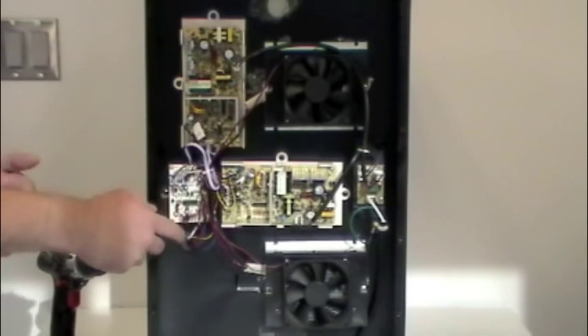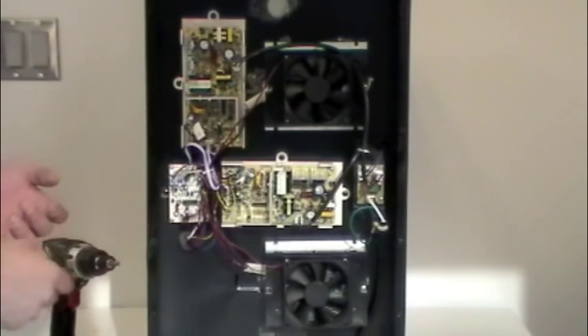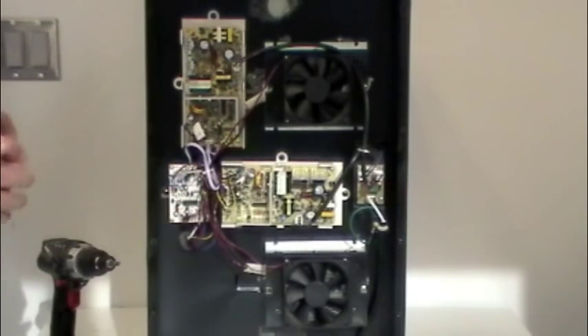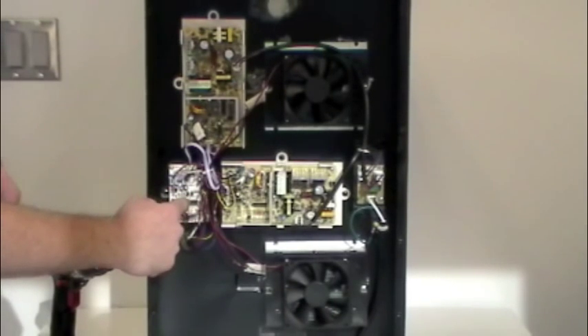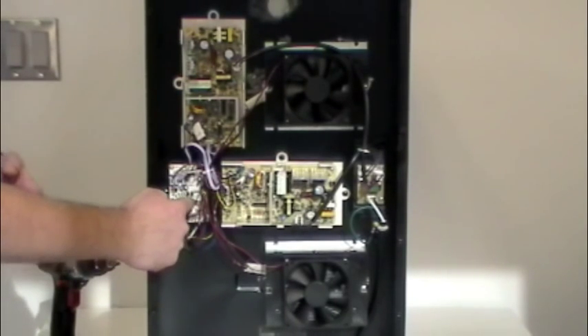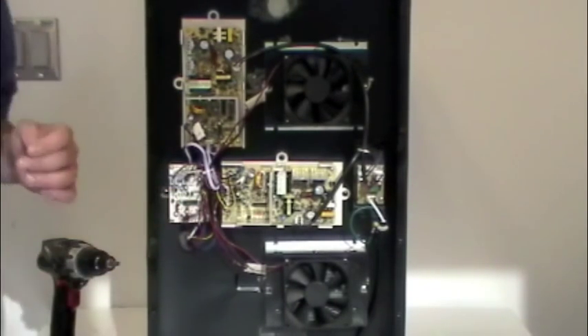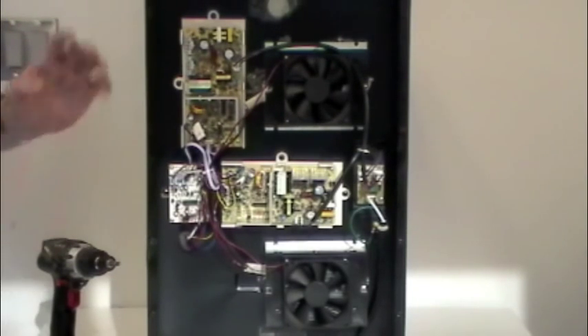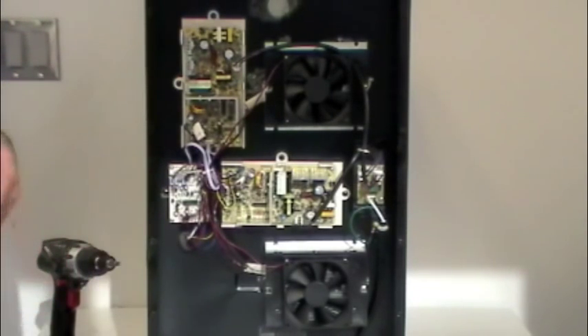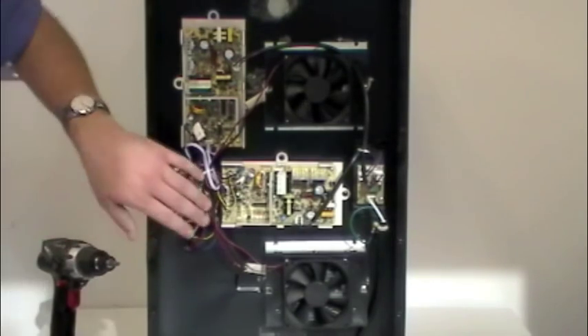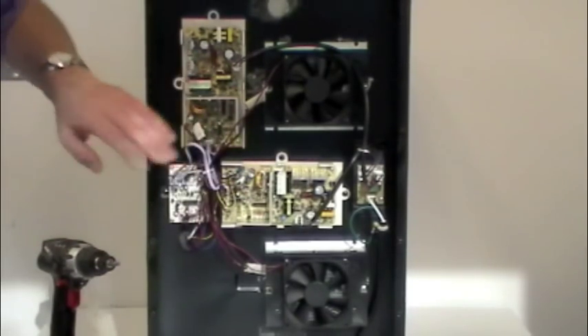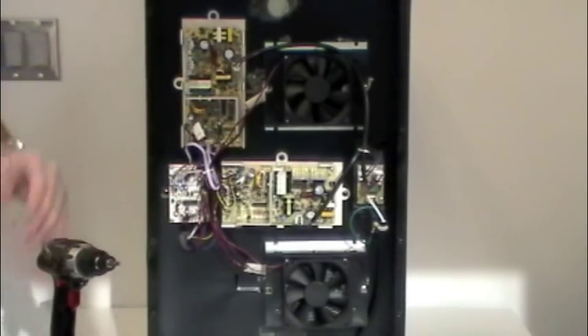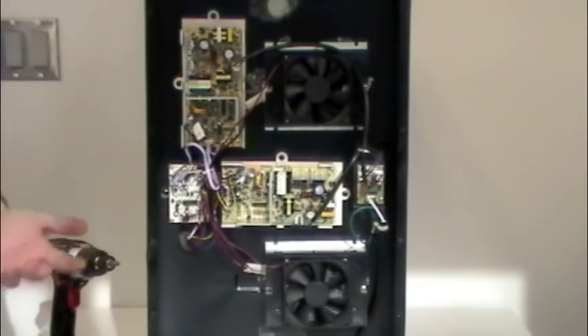If you see any burn marks in here on any of these boards, including the defrost board. And as you can see, by the way here, on this board we have an IC timer chip. So, again, it runs for a predetermined amount of time, shuts the voltage off for a certain amount of minutes so it can defrost. But if you see any burn marks or anything like that on any of these boards, obviously they need to be replaced.